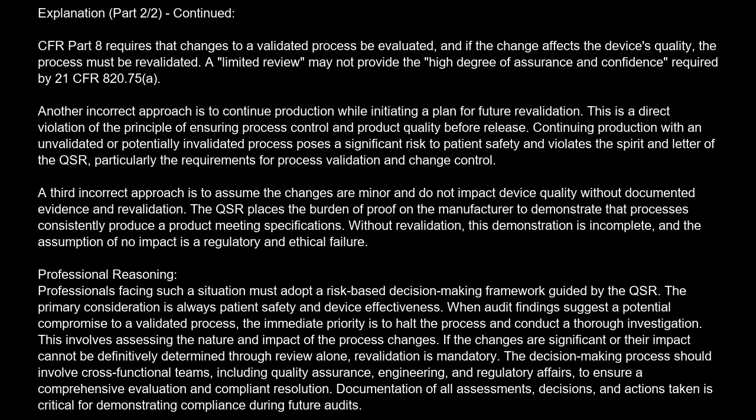Professional reasoning. Professionals facing such a situation must adopt a risk-based decision-making framework guided by the QSR. The primary consideration is always patient safety and device effectiveness. When audit findings suggest a potential compromise to a validated process, the immediate priority is to halt the process and conduct a thorough investigation. This involves assessing the nature and impact of the process changes. If the changes are significant or their impact cannot be definitively determined through review alone, revalidation is mandatory.